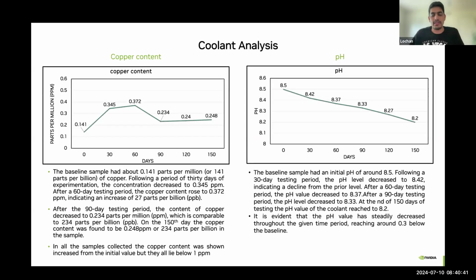Coming to the coolant analysis, we were sampling coolant every 30 days, and we were looking into different parameters like pH, conductivity, turbidity of the liquid, copper content in the liquid, and also the corrosion inhibitor, the tolyltriazole levels. The liquid coolant we were using was a PG25, and at day zero, when the coolant was sampled, we saw a copper content in the liquid of 0.141 ppm, or 141 parts per billion.